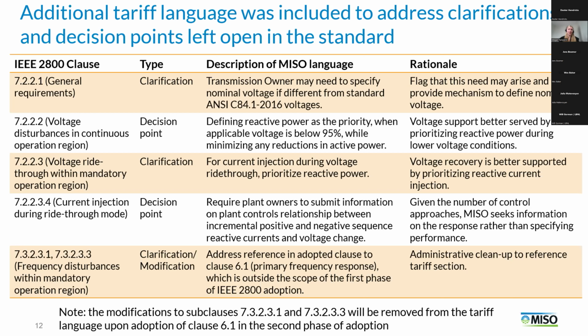Okay, and now we can take a look just quickly at the two decision points that were left open in the standard that we had to address in our tariff language. The first was for the section on voltage disturbances in the continuous operation region. So the standard states that if the plant can't deliver both active and reactive power during a disturbance in that continuous operation region, then the TS operator needs to state whether preference should be given to active or reactive power. And so in our tariff language, we specify that preference should be given to reactive power in that case.